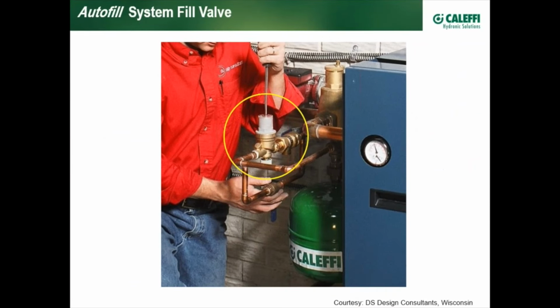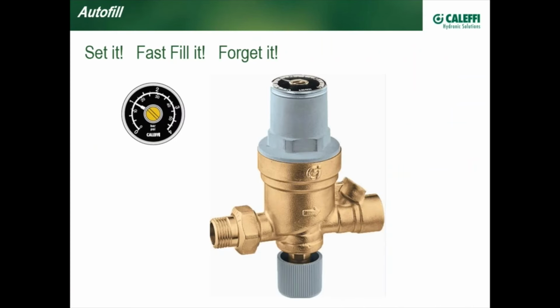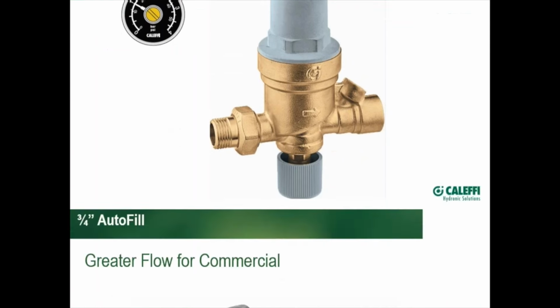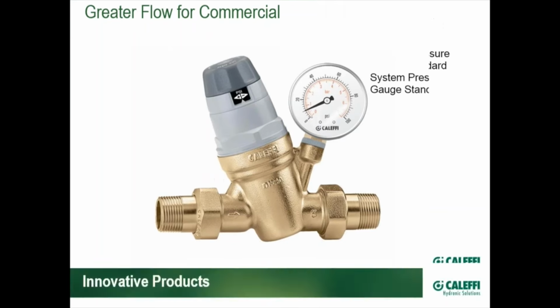Now, Caleffi has taken that cumbersome task of having to babysit filling valves out of the equation with the autofill system fill valve, as shown here. This contractor is presetting the valve before beginning to fill this system, taking a close look at the screwdriver or a penny or dime used to set the pressure you want the system pressure set to. In this case, 15 PSI, opens up the bottom. It goes into an immediate fast fill, as if the pressure reduction is basically disabled. As pressure starts to build up towards that 15 PSI, the valve slows down and turns off automatically. Set it, fast fill it, forget it. Very popular valve, both in residential and commercial sizes from Caleffi.